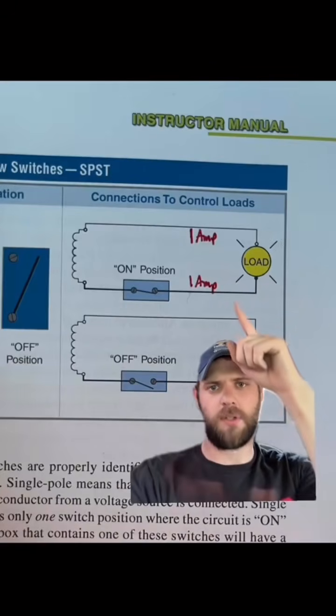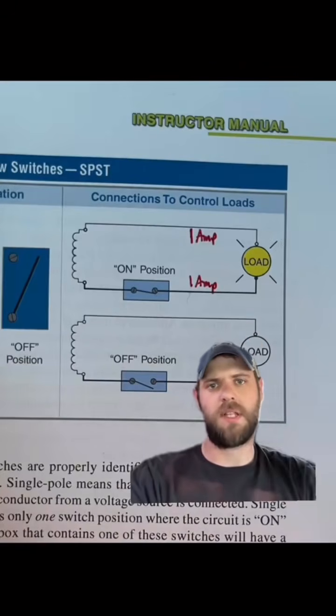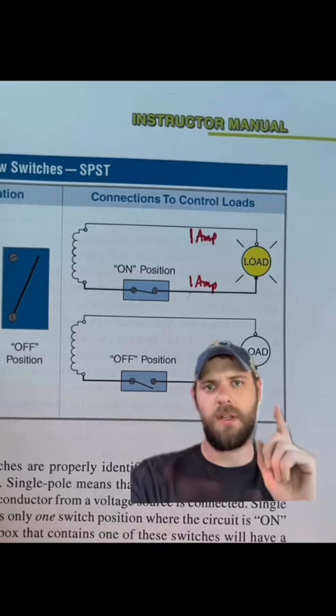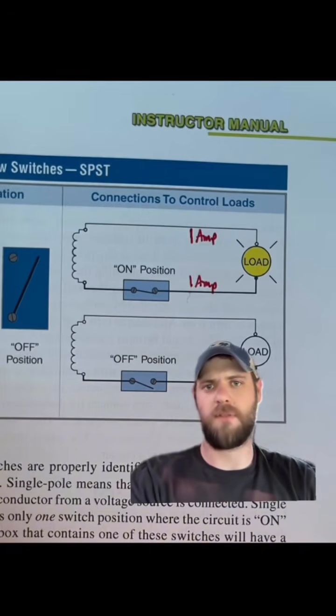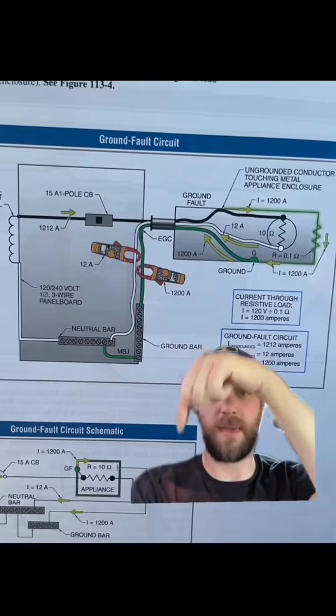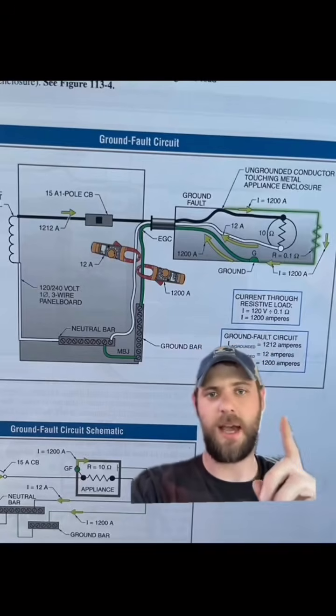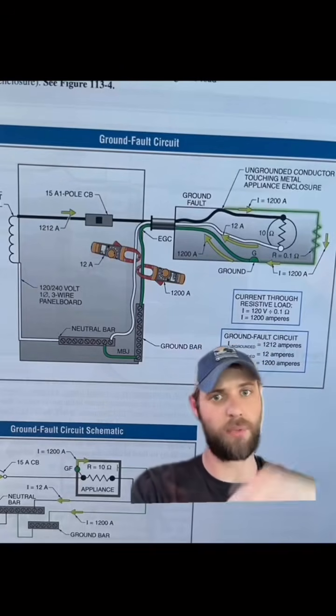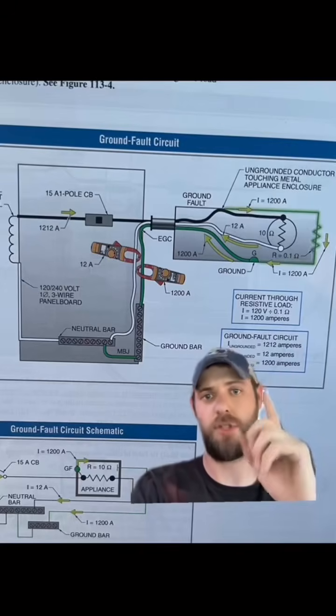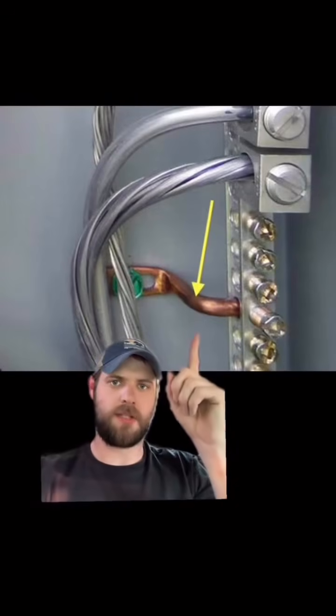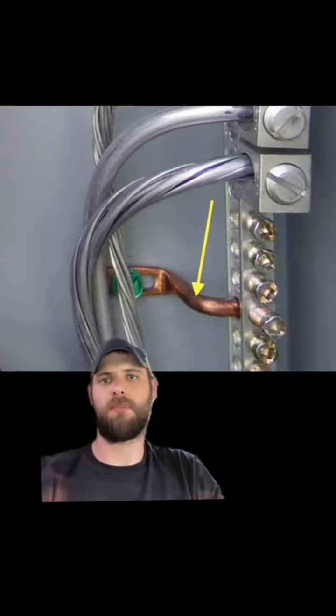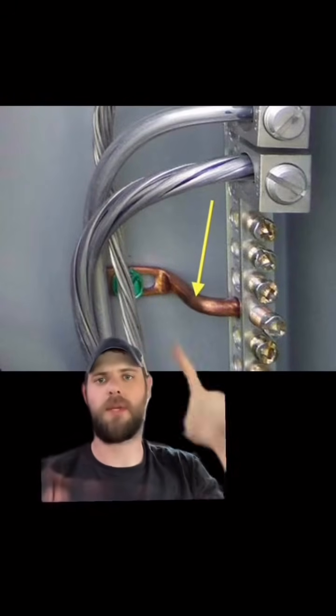Current only flows on a closed loop. Kirchhoff's current law states that the amount of current entering a node must equal the amount of current leaving a node. The same logic applies to power sources if you think about it. What goes out must come back. The notion that fault current finds its way back to earth just doesn't make any sense. I'm not saying that fault current can't flow through Earth, I'm just saying that it doesn't flow to the Earth. The main bonding jumper or system bonding jumper is ultimately what's going to complete the circuit so that fault current can find its way back to the source.